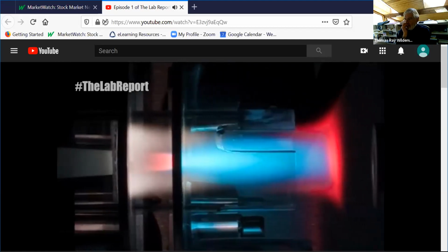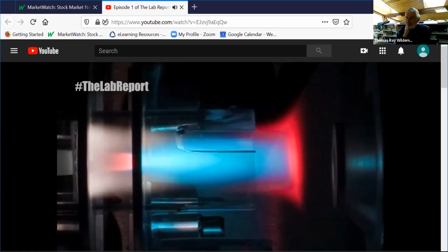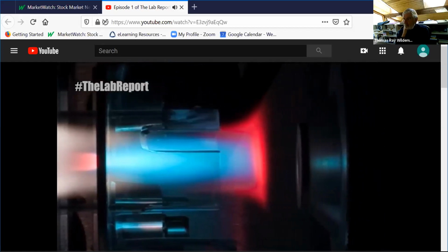When it hits the plasma, those electrons in the different orbitals are excited and they jump up to a higher energy level. But when they go back down to other transitions or where they came from, they'll emit the energy they got in the form of a photon, which is inversely proportional to the wavelength. The optics inside the ICP will then separate these photons by wavelength and then correlate the signal to that of a known calibration standard for concentrations to quantitate the metals.